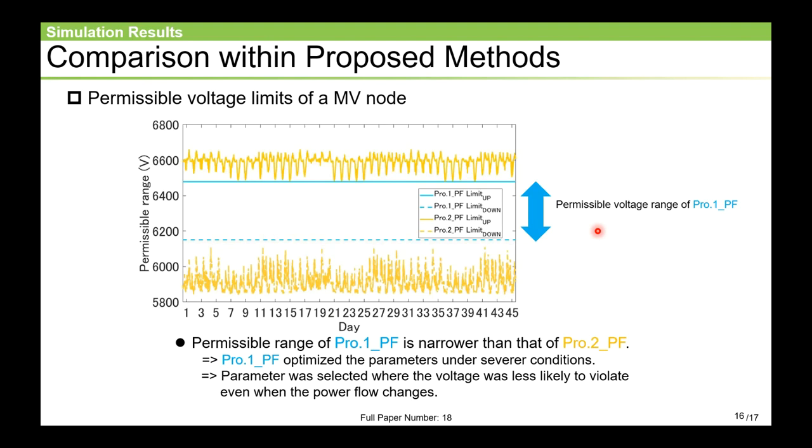Finally, we will discuss why the method using only the minimal and maximal values was able to reduce the voltage violation amount at all LV consumers. This graph shows the permissible voltage range of the MV nodes determined in step A. The area between dotted and solid line is the permissible voltage range of each method. From this graph, we can see that the permissible voltage range of PRO1_PF is narrower than PRO2_PF. In other words, the parameters of PRO1_PF were determined under severe conditions. Therefore, PRO1_PF was able to select parameters that are less likely to violate even if real conditions are different from those of data acquisition period.